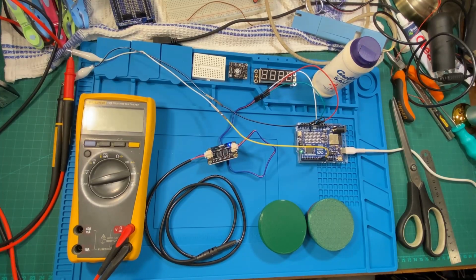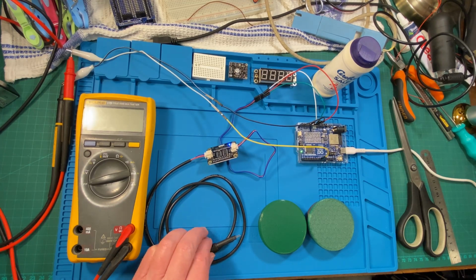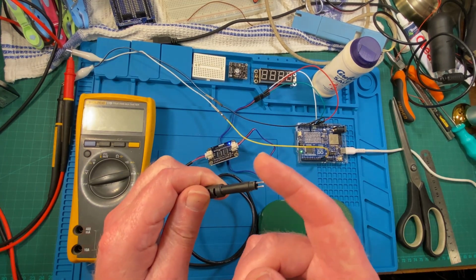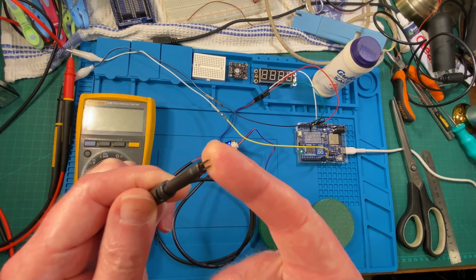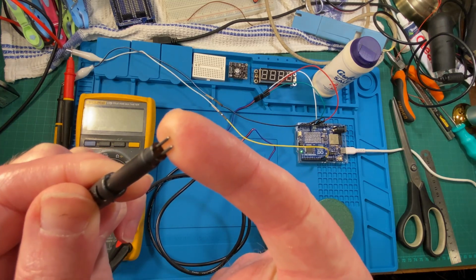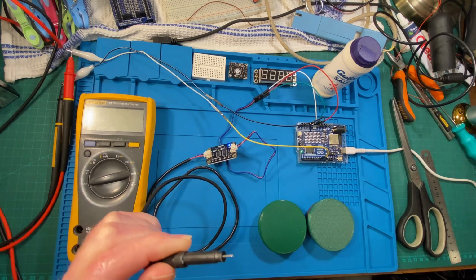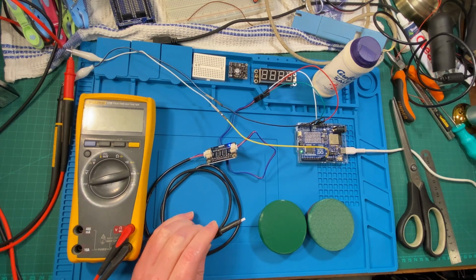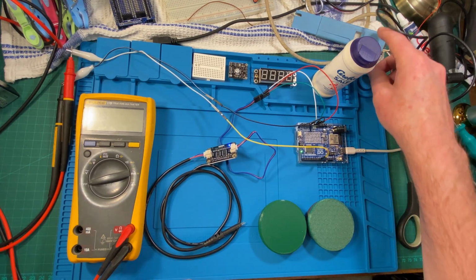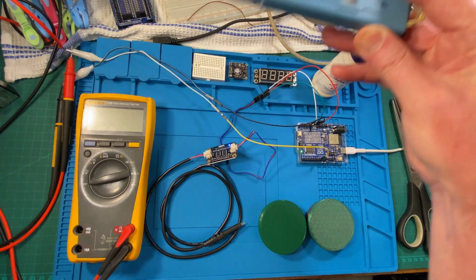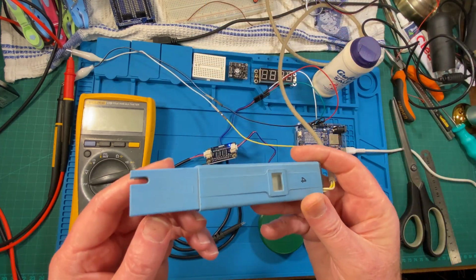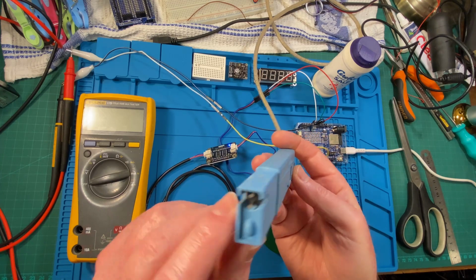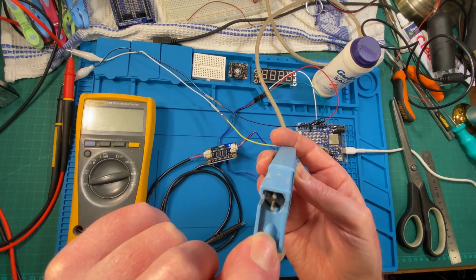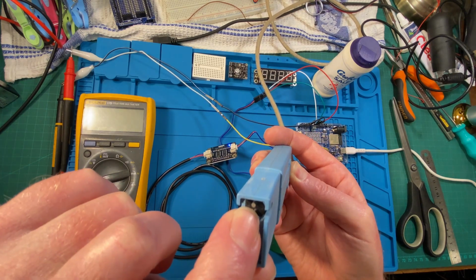So what we have here today is a total dissolved solids probe. What it does is it measures the conductivity between these 2 points over here. It's a resistance measurement. Normally this would be temperature compensated, so on a commercial instrument like this, you've got a temperature sensing bulb in the bottom beside your 2 probes.